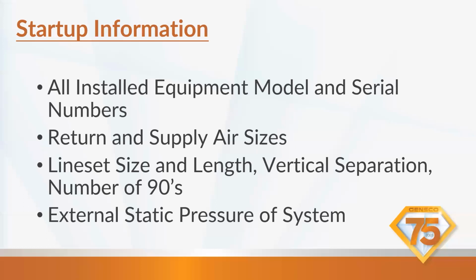Startup information. This is critical. We want to know all your installed equipment model and serial numbers. You should be recording this and logging this per site. Return air and supply air sizes, along with your filter size. You got your line set size and length, vertical separation, number of 90s, and how much refrigerant was added to the system or removed. It's always good to tally that. I used to like writing that on the backside of the service panels. That way I'd write up the startup date and how long the line set was and how much refrigerant was added or removed. It saves you in the long run, whoever has to go back there.